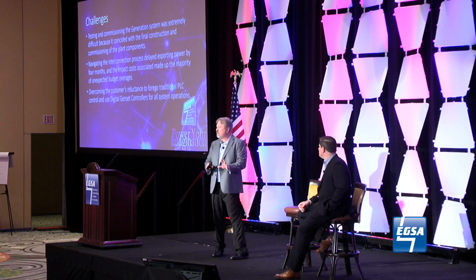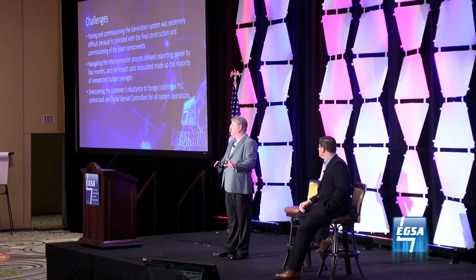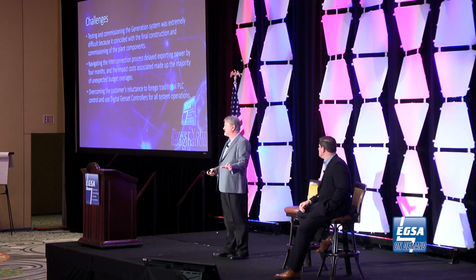We kept telling them, okay, how are you going to control the generators and the group breakers to energize the large transformers with the groups? I have to delay those closing to a dead bus until we have enough online to energize those 5 large transformers. And the engineers finally saw the light and said, okay, we'll put those in, and there's actually no PLC control from an external PLC in this entire system.